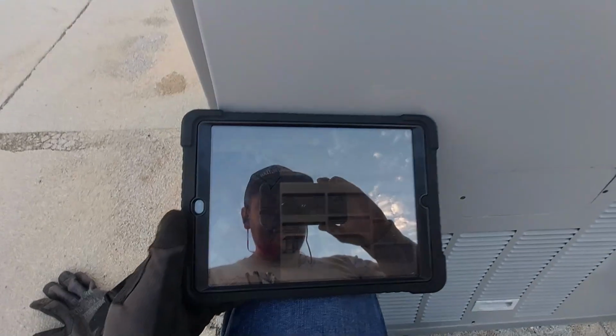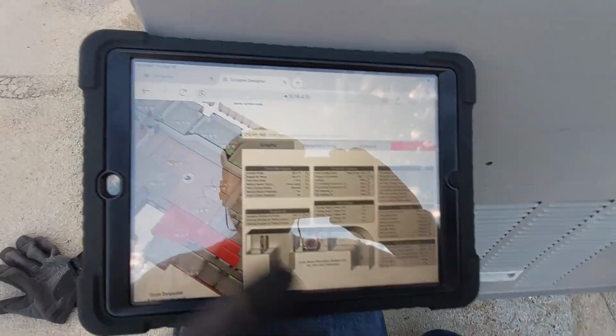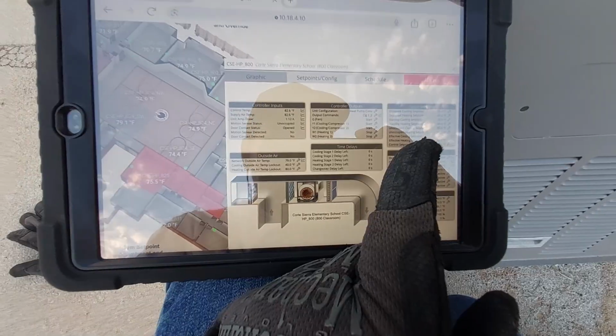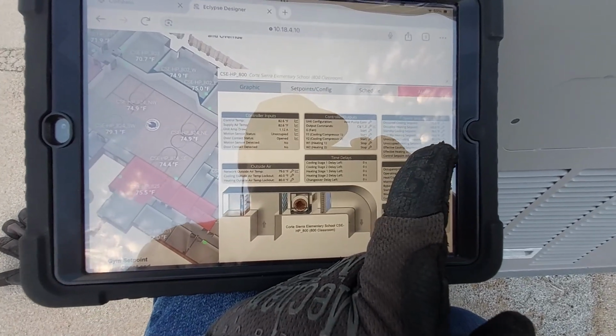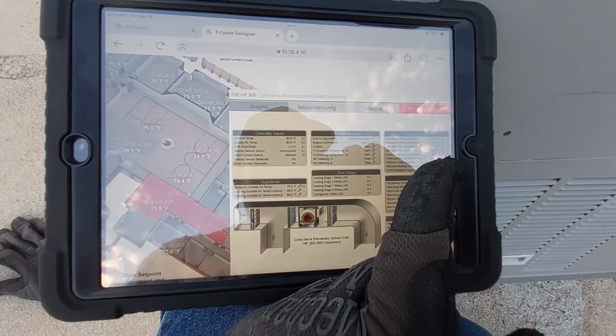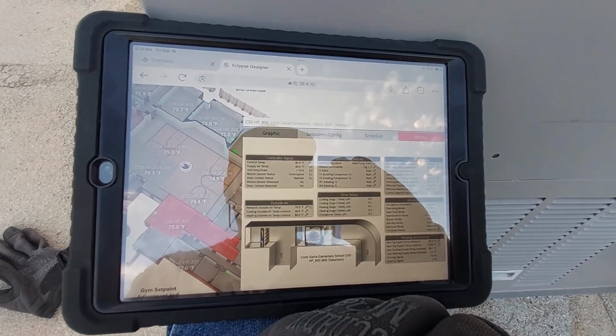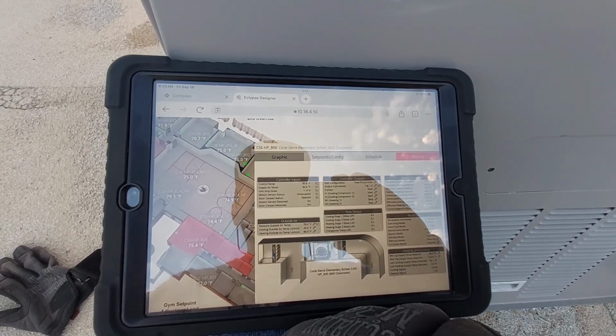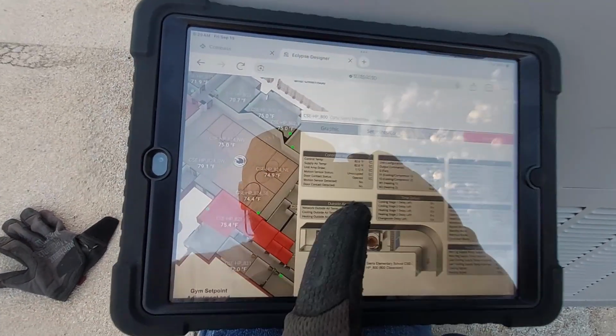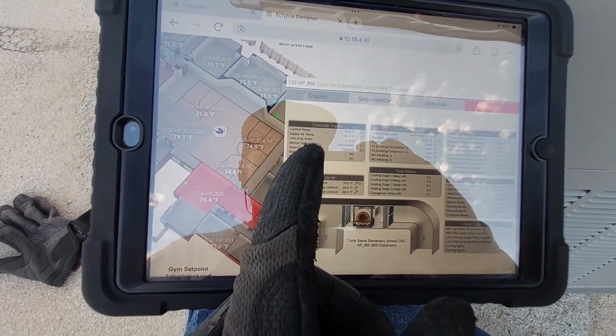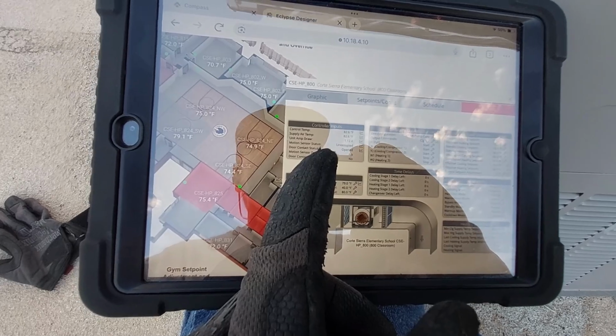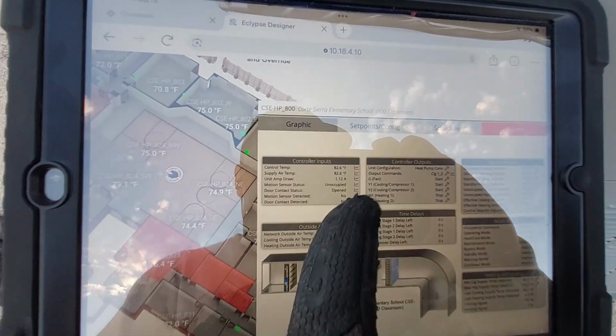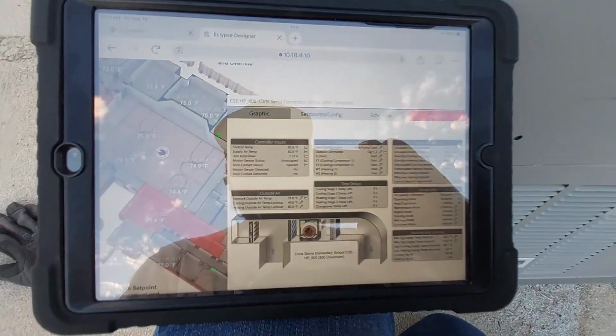Alright, so here's what's going on. Pretty much this is the software I use. It's called Eclypse. I'm not sure if you guys can see that, but we have the occupied cooling set point set at 75 degrees, right? If you're thinking about it like a thermostat in a residential home, that thermostat would be set to 75 degrees, okay? Here I have control temp. That tells me the temperature currently at the thermostat. So right now it's showing me 82 degrees, and then supply air temp showing me 82 degrees.